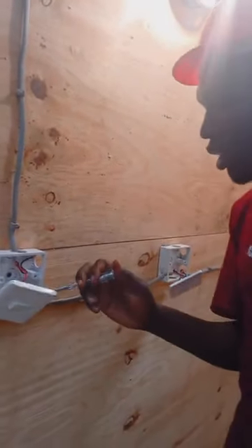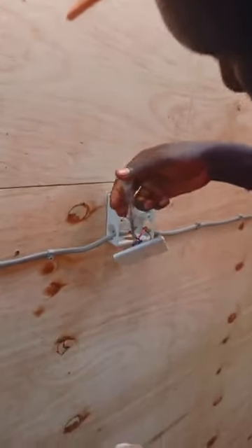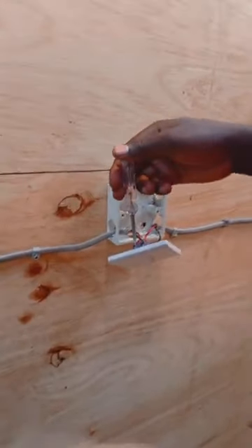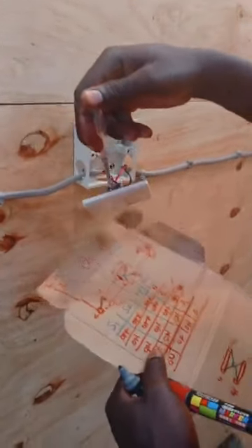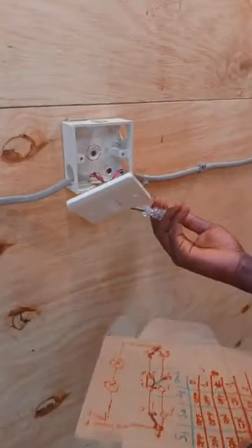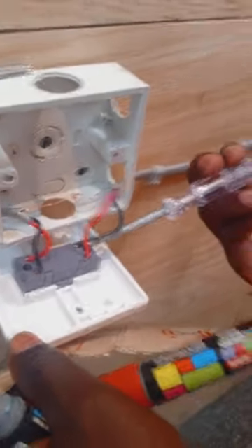So it is L1 which is supplying power here, and meaning our power is going to be here in this second thing. And when this intermediate switch is in off position, as you can see, it is continuous with this one, with the L2 of the second terminal. This one, you can see there is power.